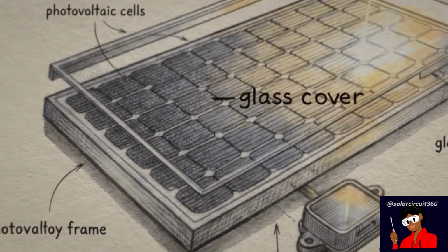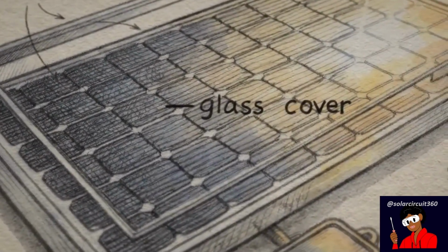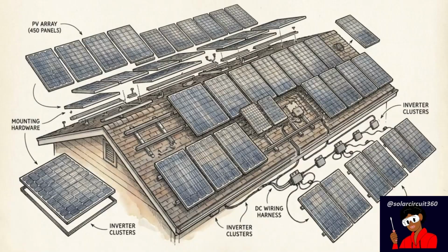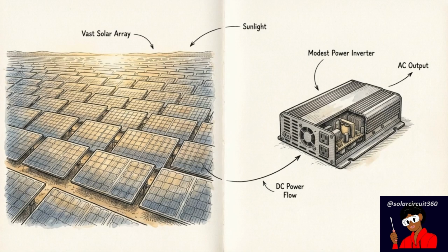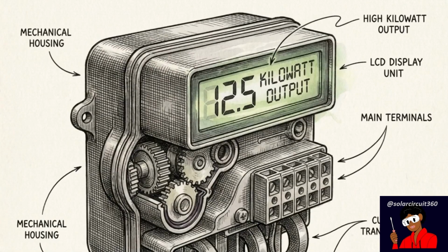Most solar systems out there don't underperform because of bad weather. They lose power because of intentional design decisions. One of the most common practices in the solar industry is oversizing. This is when an installer pairs a large DC solar array with an AC inverter that has a lower capacity rating, with the specific aim of boosting the total daily energy yield.